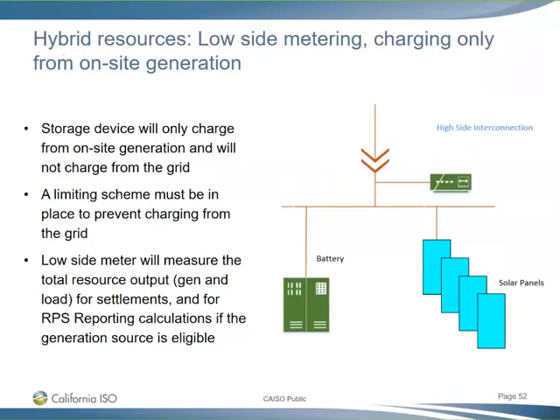The next one is low-side metering with charging from only on-site generation, again for hybrid resources only. The storage device can only charge from on-site generation, not the grid, so you need a limiting scheme. You'll have 1 meter on the low side of the transformer, shown by the green box with dots in this diagram.